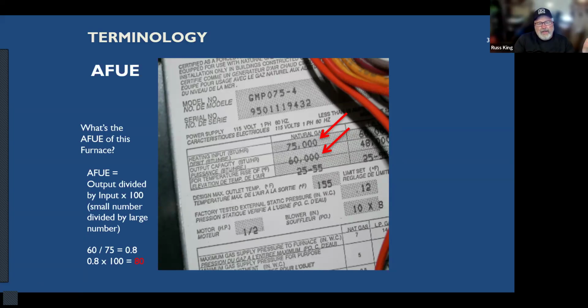Now think about it though. Where's that heat going? If you're putting in 100,000 on this furnace here, you're putting in 75,000 BTUs worth of heat, and it's burning. Presumably, all the gas is burning. You don't want there to be any unburned gas, but all that gas is burning. But only 60,000 BTUs is actually getting into the house. All right. Where is the rest of that heat going?